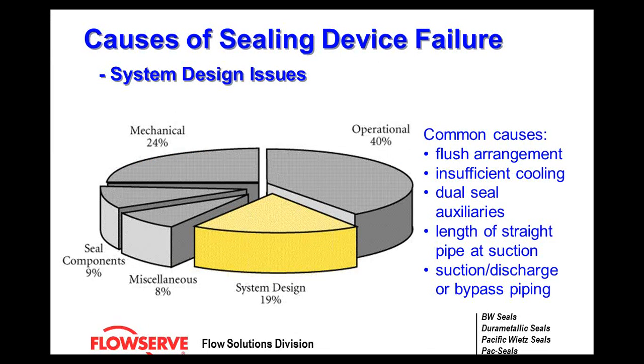System design common causes: seal flush arrangement — do you have the proper seal flush for the type of seal and system you're operating in? Insufficient cooling is again indicative of a flushing problem. Dual systems require auxiliaries; the auxiliaries have barrier fluids. Is your auxiliary seal pot in the right location? Do you have the right instrumentation? Is it piped correctly? All of those will cause seal failures.